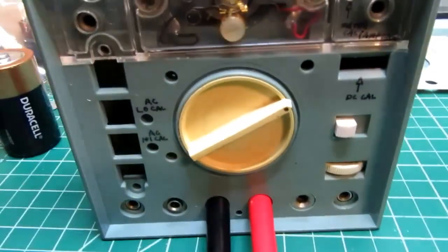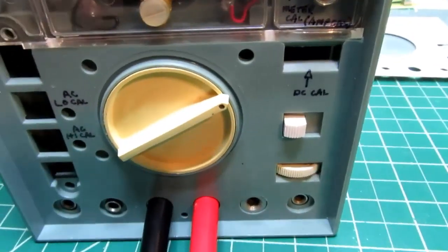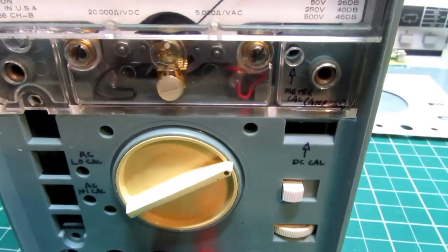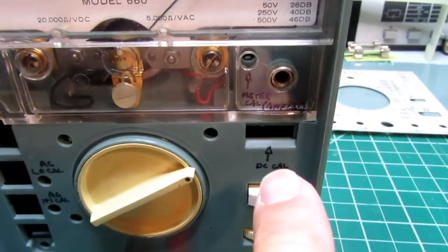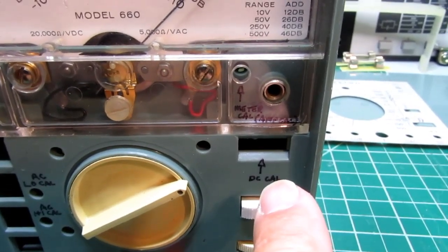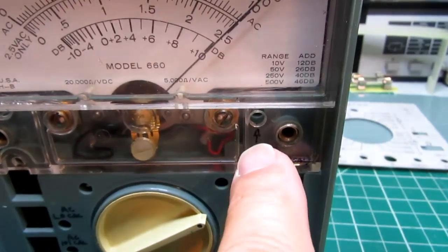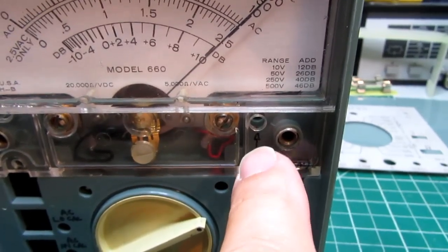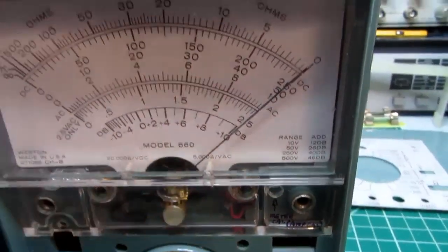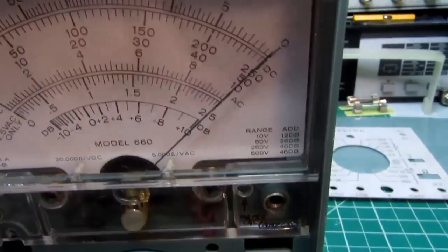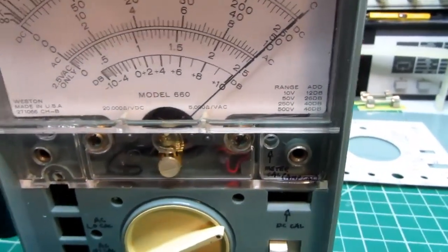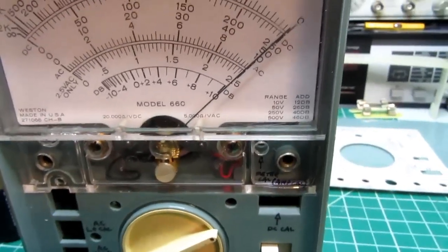I forgot that the DC cal pot is also part of the equation. I can't easily bypass that, so what I did is set this to the middle of its range and then readjusted the first trim pot with a 10-volt verified signal to get a 10-volt reading. Hopefully that'll make a little more sense. I didn't have to change it much.